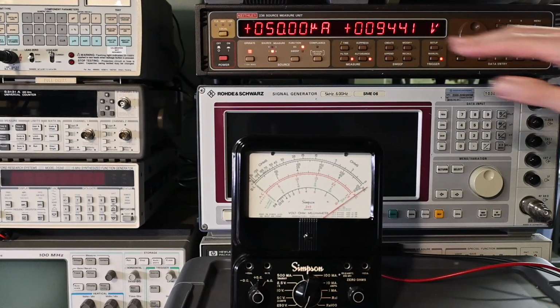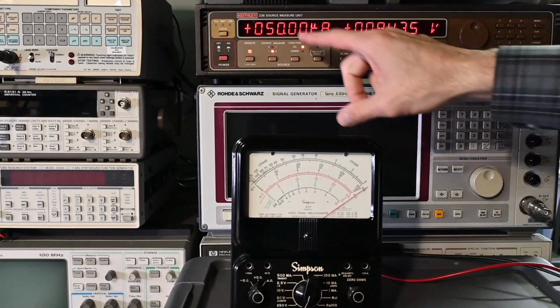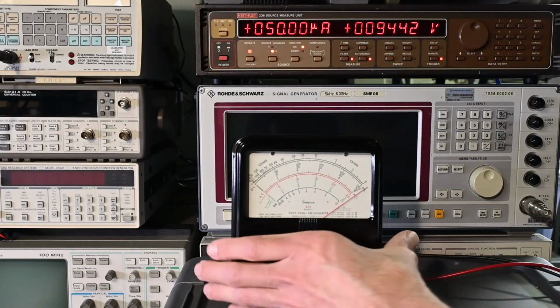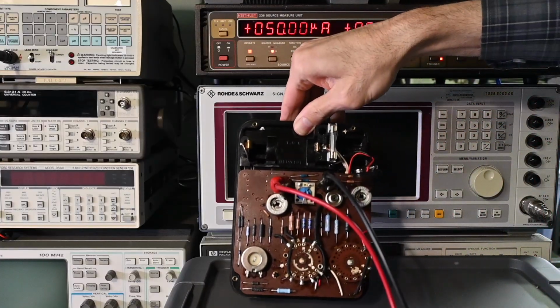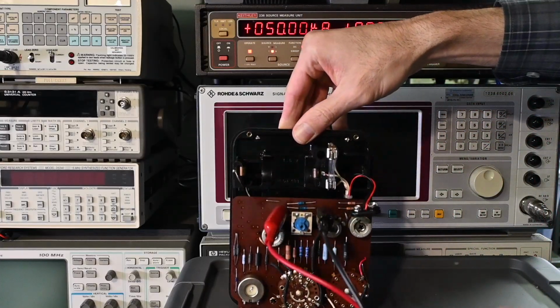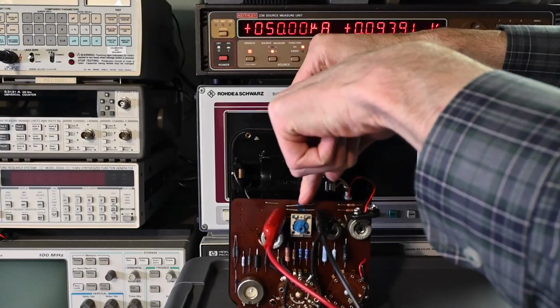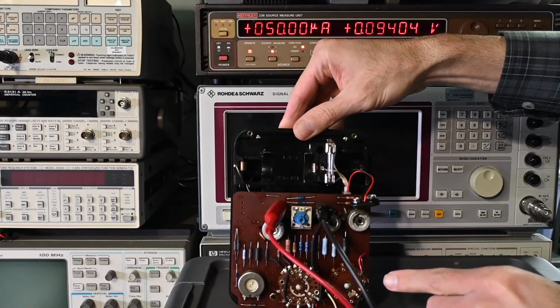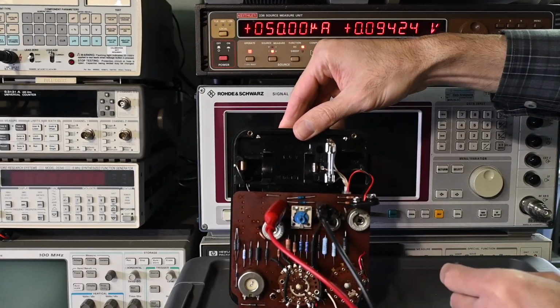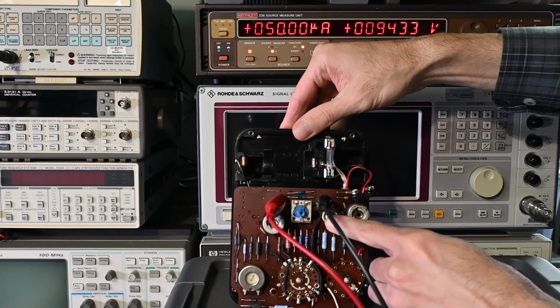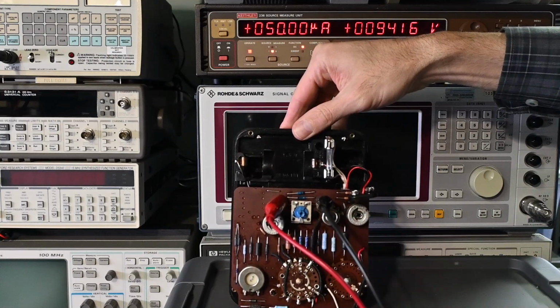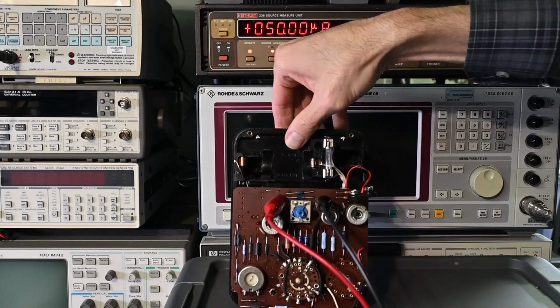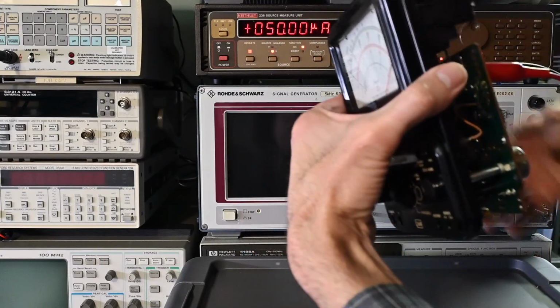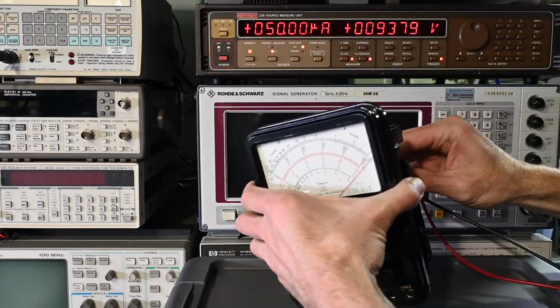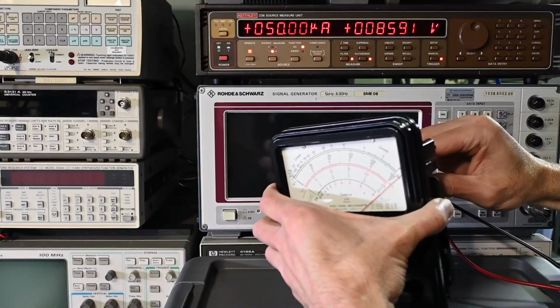All right, so the Keithley 236 is in the constant current mode, 50 microamps, and you can see the test leads are connected to the studs on the back of the meter. And I'll be making the adjustment on this potentiometer right there, and I don't need a tool. I can just turn that with my fingers. And then the second potentiometer is this one, and I'll have to use a little screwdriver to adjust that potentiometer. All right, so get this turned back around here. You can see, make sure that is on there secure.